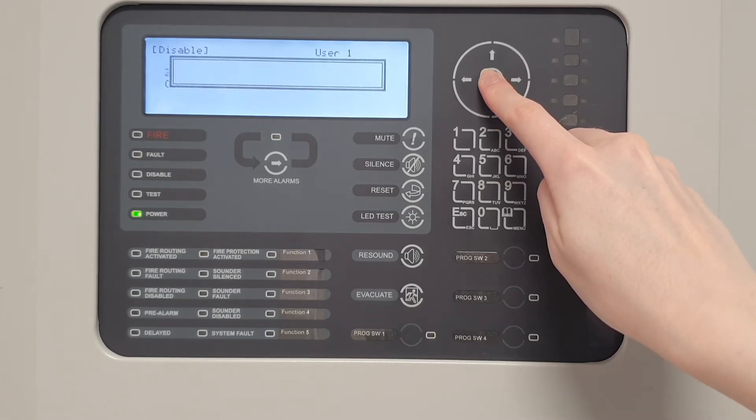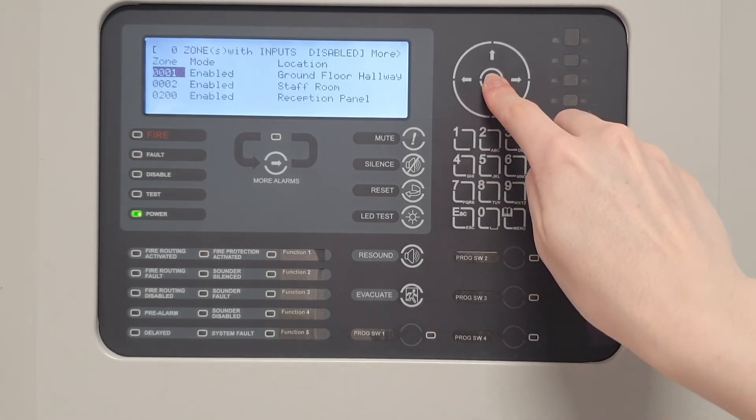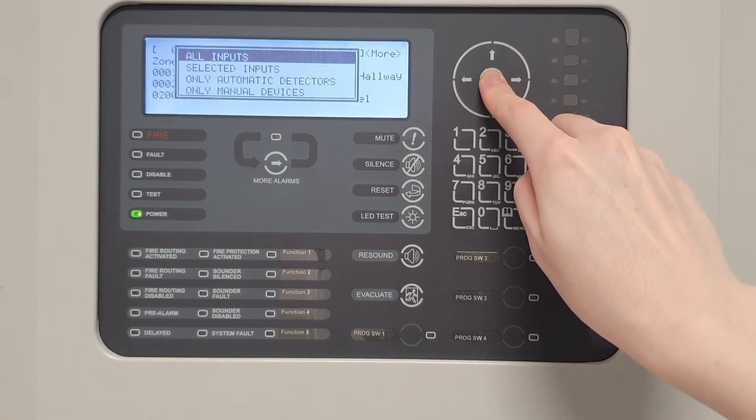You may be prompted for a password to access this menu. The default is 7654. Once in this menu, scroll down to the desired zone, then press tick and choose which inputs from the list. All inputs will disable all inputs within that zone.